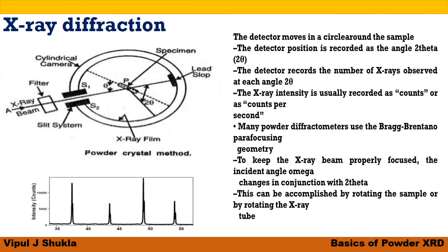As the sample and detector are rotated, the intensity of the reflected X-rays is recorded. When the geometry of the incident X-rays impinging on the sample satisfies the Bragg equation, constructive interference occurs and a peak in intensity occurs. A detector records and processes this X-ray signal and converts it to a count rate, which is then output to a device such as a printer or computer monitor.